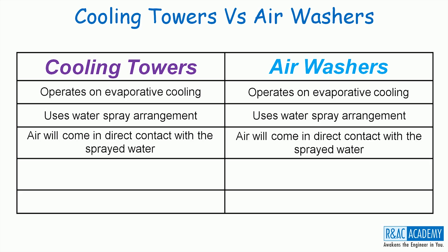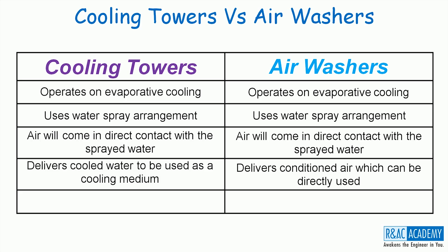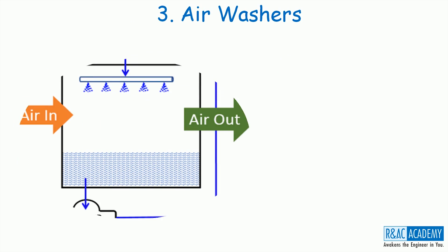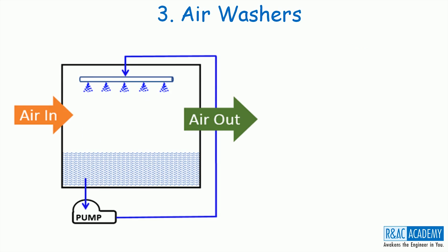Then where exactly do these two differ from each other? The cooling tower delivers cooled water to be used as a cooling medium, while the air washer delivers the conditioned air which can be directly used in air conditioning systems. Also, the cooling towers are placed outdoors or on terraces. On the other hand, the air washers are placed indoors in order to avoid contamination of conditioned air with dust, dirt, etc. The air washer has a spray arm to spray water from the top. Air will enter from one side, interacts with the sprayed water and then exits.